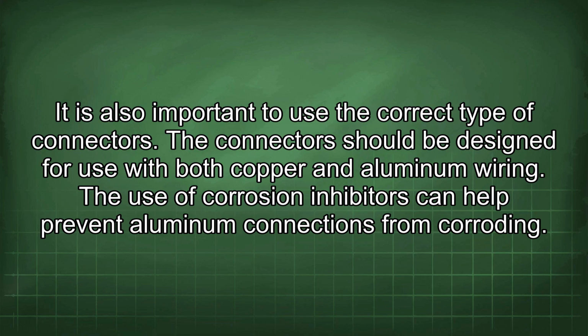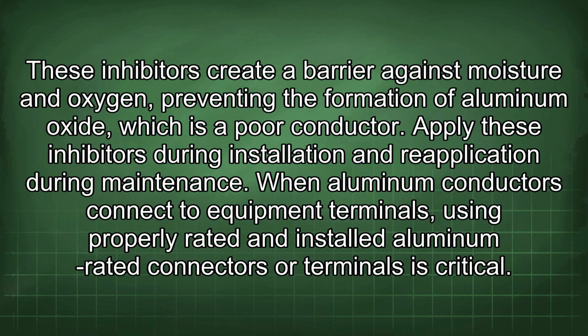The use of corrosion inhibitors can help prevent aluminum connections from corroding. These inhibitors create a barrier against moisture and oxygen, preventing the formation of aluminum oxide, which is a poor conductor. Apply these inhibitors during installation and reapply them during maintenance.